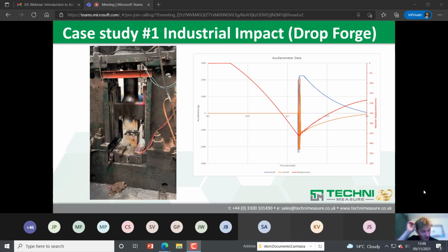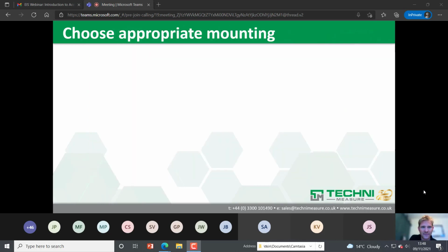The red line you can see on the graph on the right is the actual displacement of the ram as it moves down, and you can see the impact there. And then there are two accelerometers. This is actually before we implemented the charge attenuation circuit. We were measuring plus or minus 2000 g. Something you can see here as well is the discharge time constant, which is the time it takes for the charge electronics to settle down after having measured an impact, and they tail off. That's something to take into account as well, especially if you're looking at repeated impacts or cyclic shock type events. So there's an example of an industrial impact.